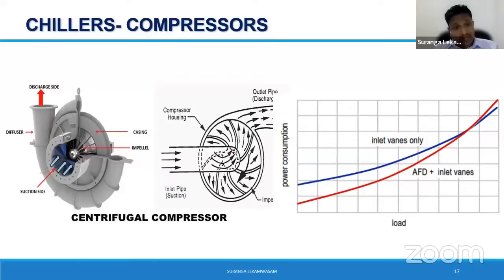Well, on top of that, you have the centrifugal chillers. You can find centrifugal chillers if you are exceeding a capacity of 500 ton. These are bigger machines. There is a big difference between all the compressors we discussed so far and the centrifugal compressor, because the other compressors we discussed, like screw, scroll, rotary, are all called positive displacement machines. When they run, there must be a flow. But here, this is a centrifugal machine, similar to your centrifugal pump. You can run the pump for a short period without any flow, forcing the discharge. So this is a rotodynamic machine, not a positive displacement machine.